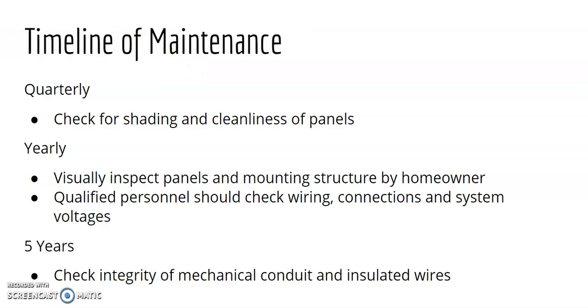Sorry about that. And we have created an outline plan of maintenance to be performed on the system, both visually by the owners and for those that will need a qualified electrician to perform the work. So quarterly, our homeowner will check for shading and the cleanliness of the panels. Yearly, the homeowner will visually inspect the panels from the ground. They will visually inspect the panels and mounting structure. Also yearly, they will have qualified personnel out to check the wiring, connections, and the system voltages. Every 5 years, they will again have a third-party contractor check the integrity of mechanical conduit and insulated wires. Any maintenance that is corrective will be done on an as-need basis.